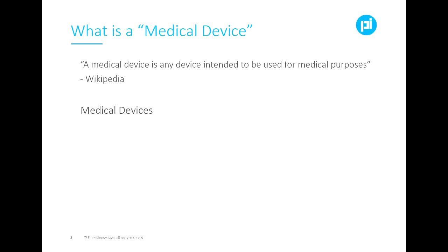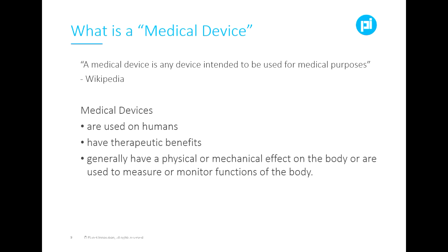The Therapeutic Goods Administration of Australia has a more useful definition, where medical devices are used on humans, have therapeutic benefits, and more verbosely, generally have a physical or mechanical effect on the body and are used to measure or monitor functions of the body. So it's very explicit about what a medical device is going to be. And that's now very constrained about what you need to do to develop one of them.